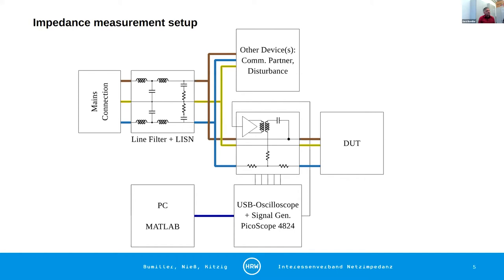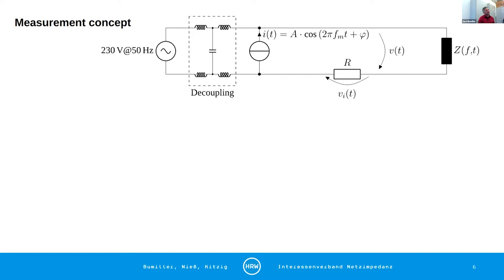Then we have in the middle our measurement box with current source and measurement shunts. We measure the voltages over the shunts. We generate signals with a USB oscilloscope and PicoScope, and we control all of it from a PC. We can connect in parallel on line side other devices like communication partners, disturbances, low impedance, or something that affects the device under test.